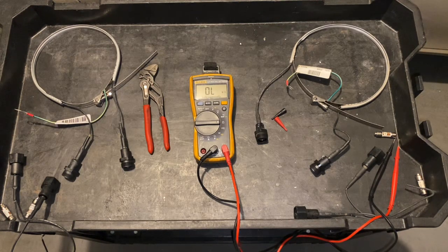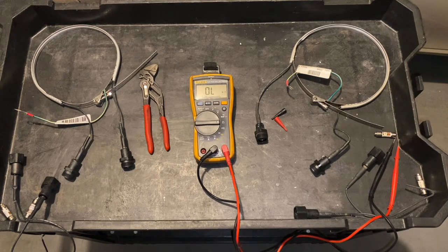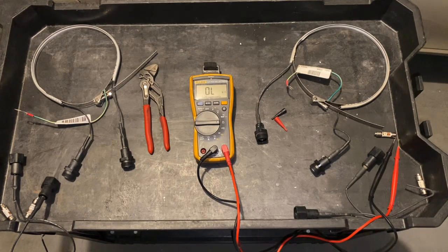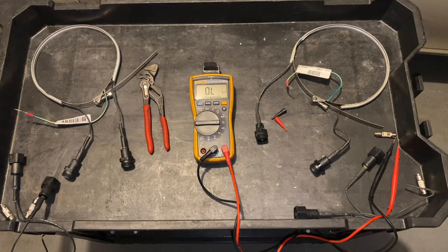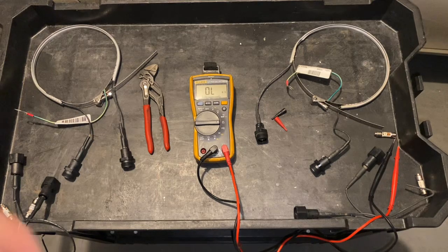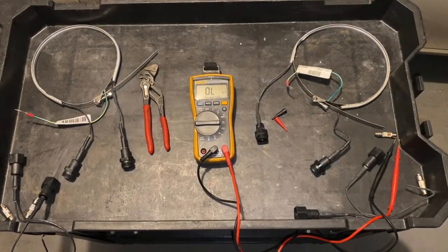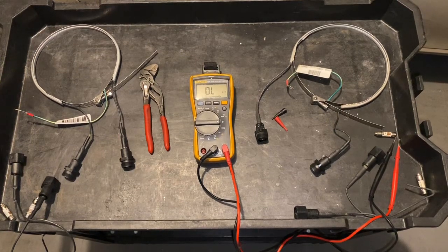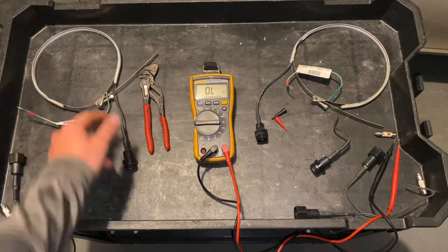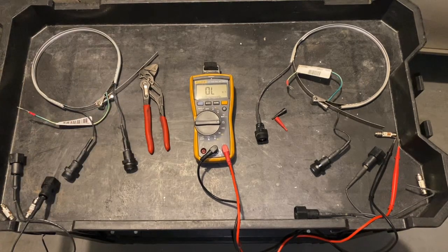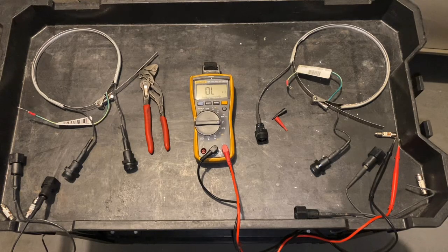As far as why crankcase heaters are important, one thing a lot of people don't know is if you don't have a crankcase heater or any way to manage liquid flood back or oil return, what's going to happen is on startup, you're going to have liquid for a brief time going into your compressor.